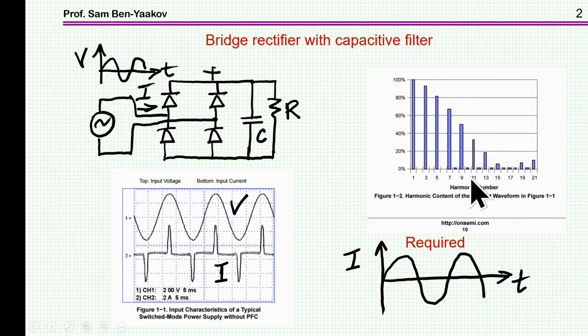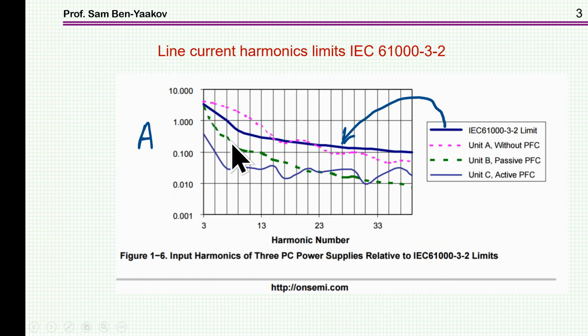Now, there are standards enforced in just about every country which require that the magnitude of these harmonics be fairly low, so that the current will be just about like a sinusoidal waveform coming from the line. Here is the limit for the IEC 61000 norm. So what it says is, say for the 13th harmonic, the magnitude of the current of this harmonic will not exceed this value, in amps. If you are using a regular rectifier, you are violating this limit, and you do need some sophisticated rectification scheme like active power factor correction, which we are going to talk about, in order to be below the limit.